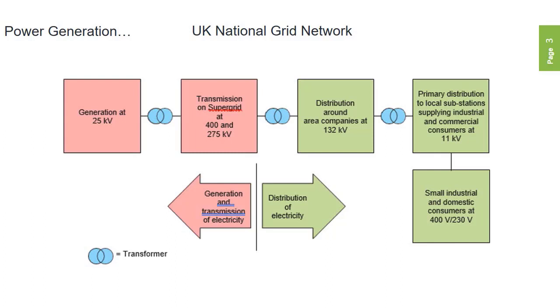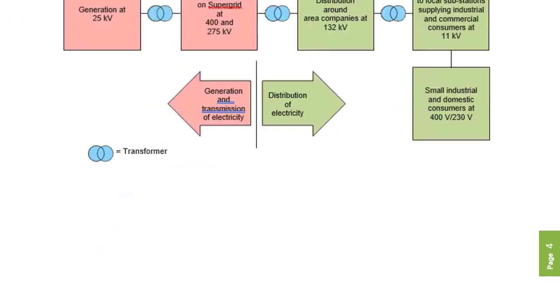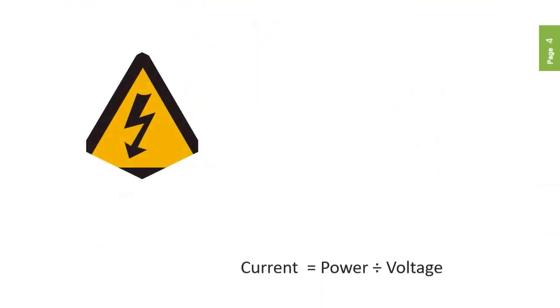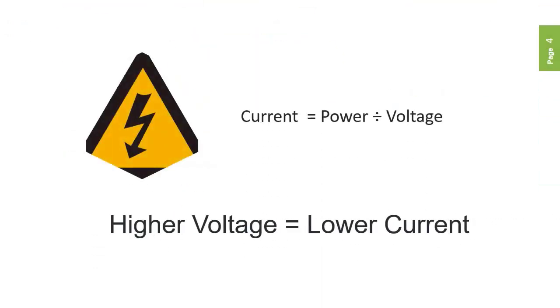This higher voltage is used for many reasons. Firstly, because current is equal to power divided by voltage — or I equals P divided by V — by increasing the voltage, we reduce the amount of current flowing in the conductors, which in turn allows for a smaller conductor to be used.